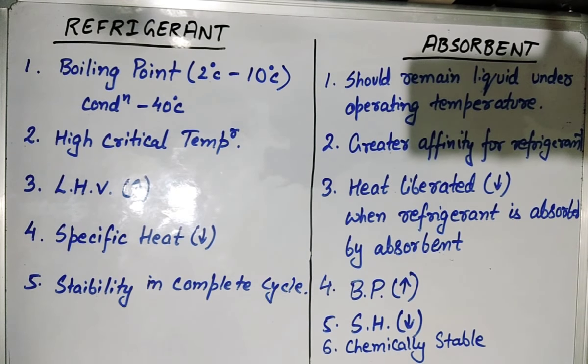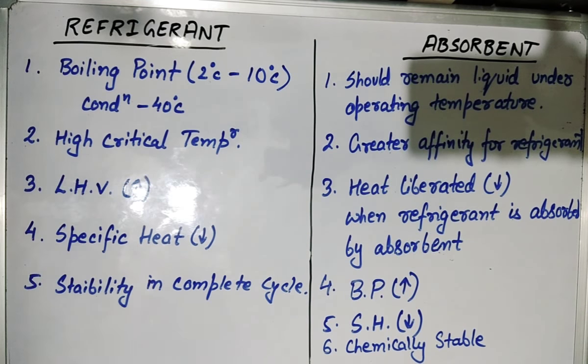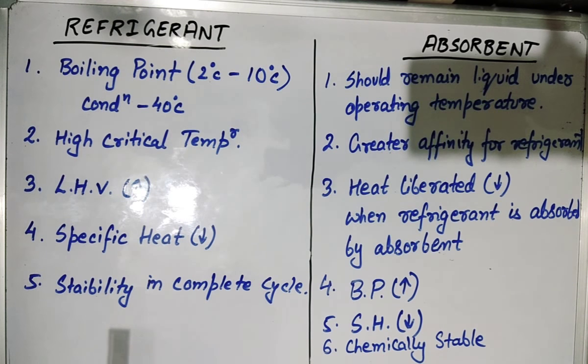The first thing is what is the selection criteria of a refrigerant? The first point is the boiling point. The boiling point of the refrigerant should be in the range of 2 degrees to 10 degrees Celsius at an operating condition of 40 degrees Celsius. That means it should have a low boiling point.